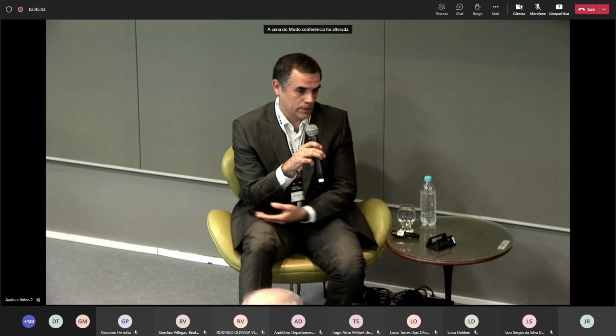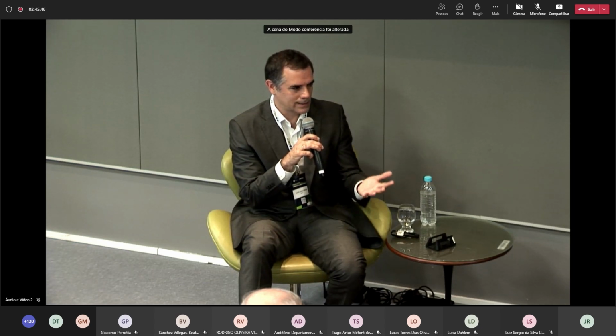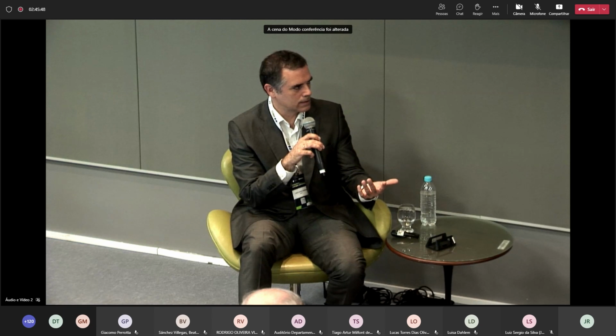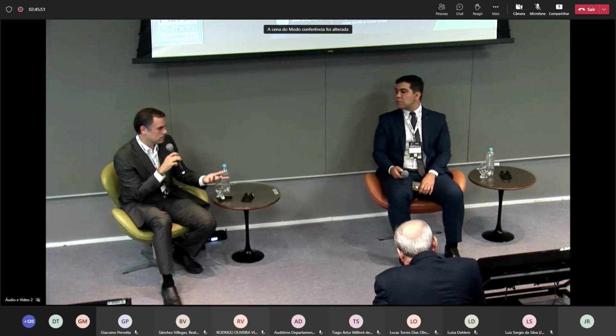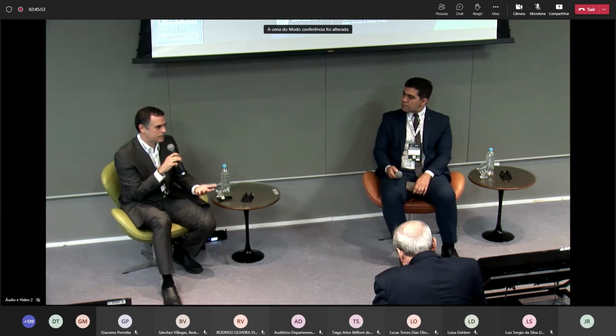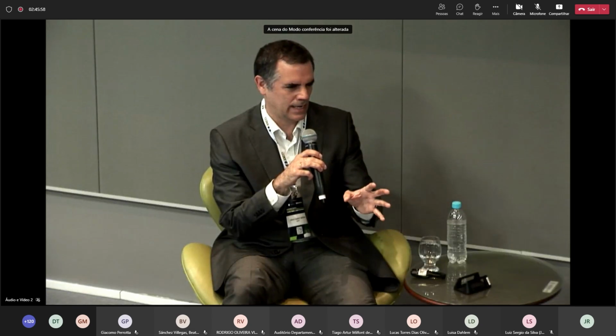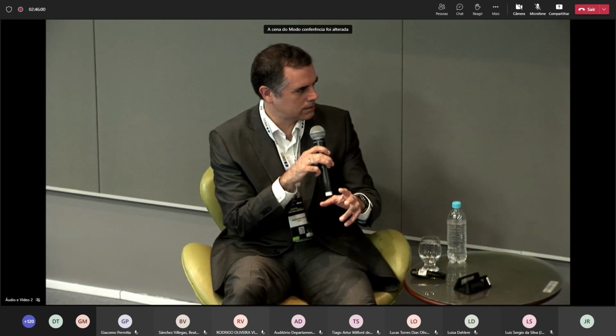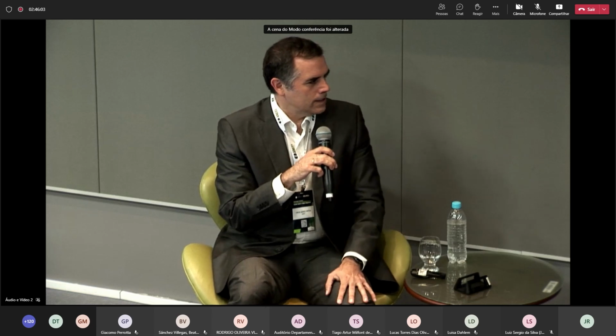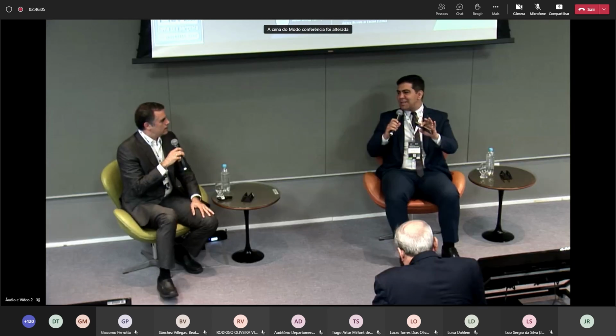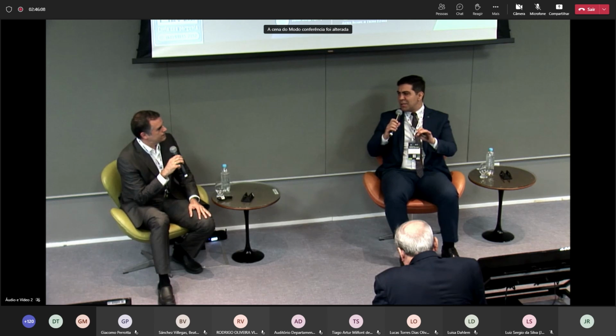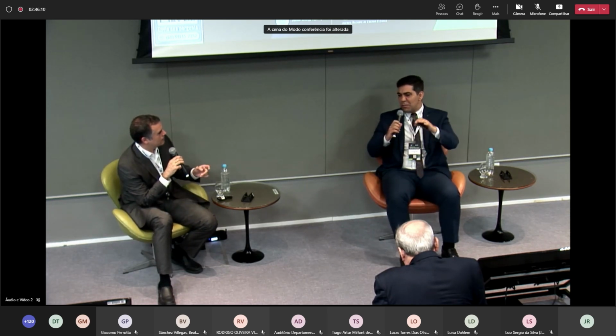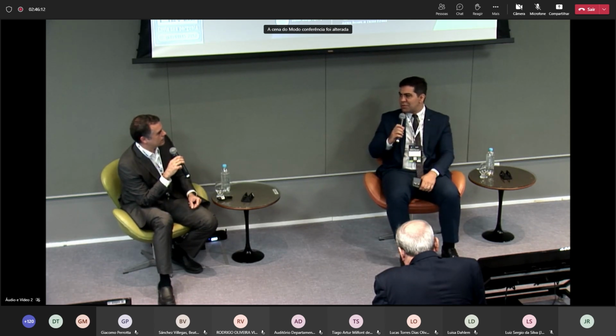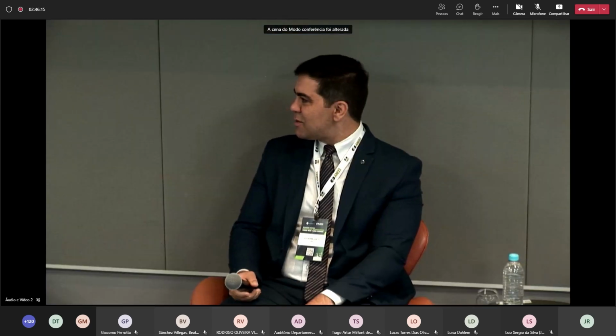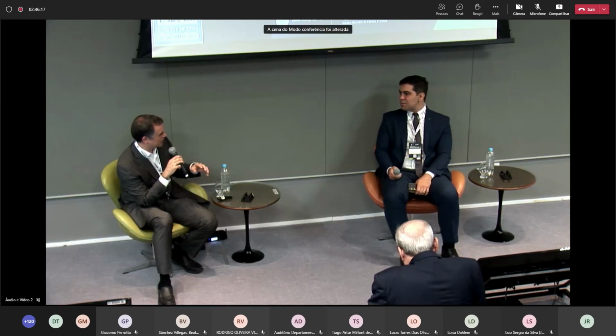But theoretically, if there is a fault, all the inertia that grid forming can provide could solve the problem. I think the output of that report is that if we locate, I don't remember exactly, maybe 9 synchronous condensers... they signaled 9, but only 3 were indicated as a zero-regret solution. The other ones will be handled by EPE as a structural solution. I think we are considering 3, but the report mentions around 9.